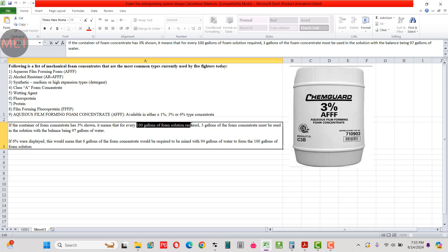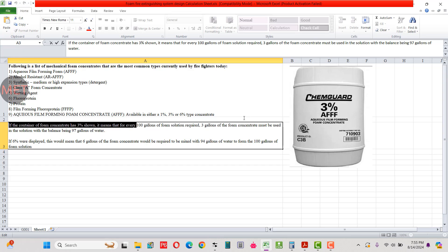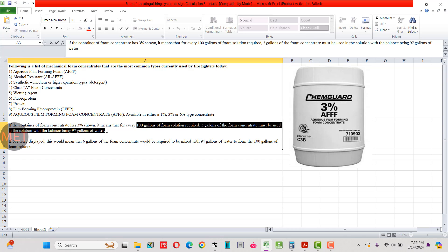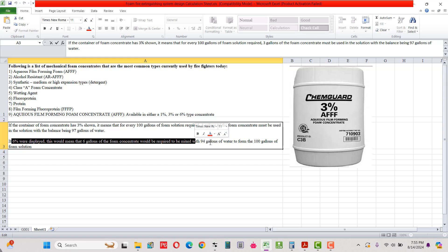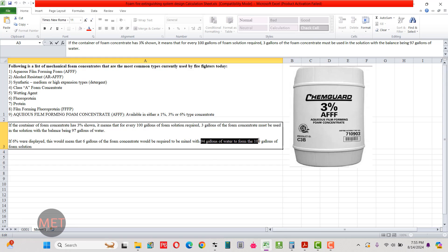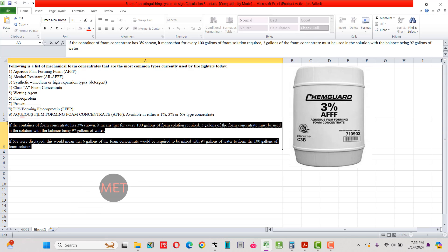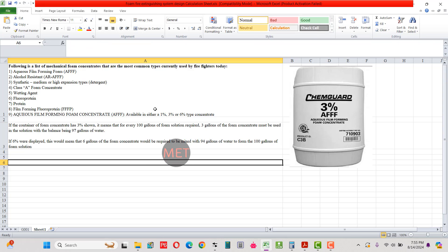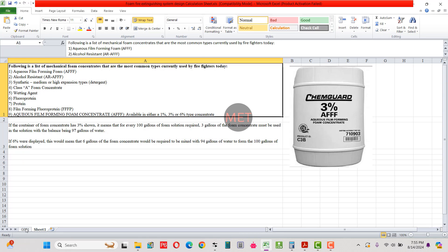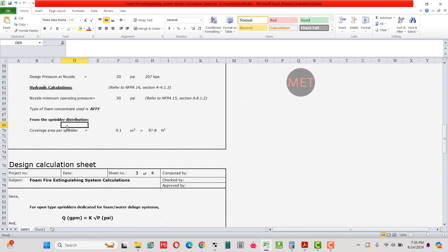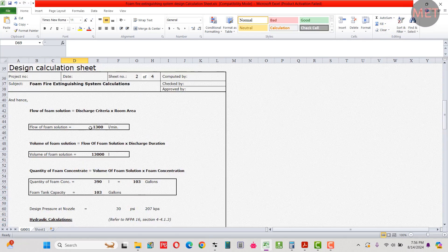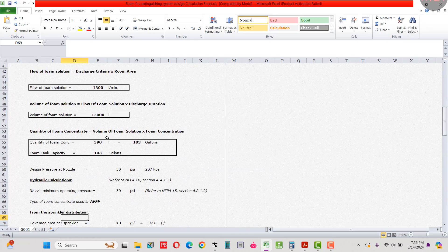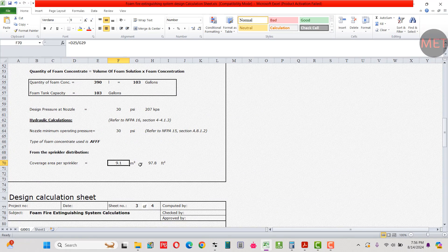For sprinkler distribution, the minimum coverage area per sprinkler is 9.3 square meters. With 22 sprinklers covering 200 square meters total, the actual coverage area per sprinkler is 200 ÷ 22 = 9.1 square meters, which converts to 97.8 square feet.